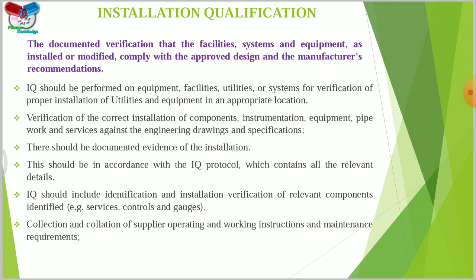So what are the requirements during the IQ? We have to verify all the calibration of supporting instrument accessories, the MOC of the equipment, and identified measuring, control, indicating devices should be calibrated on site unless otherwise appropriately justified. The calibration should be traceable to national or international standard. Traceable certificate should be available. It means you have to attach the supporting document like calibration certificate up to 2 levels. It means the vendor provided and the master's master. So these are the documents you have to attach with this document.